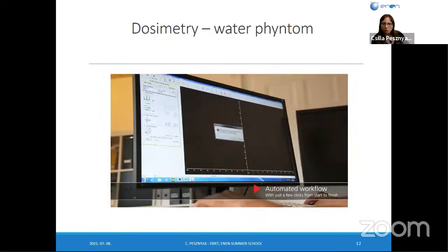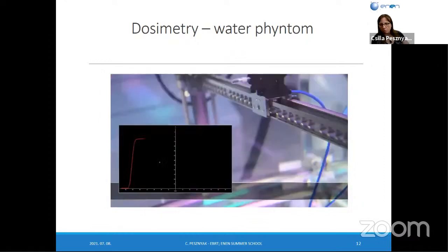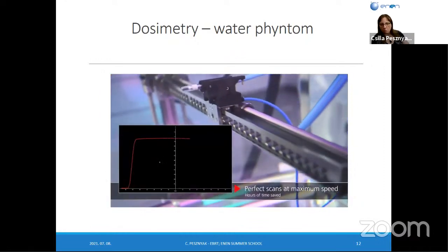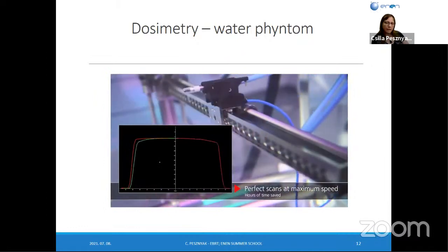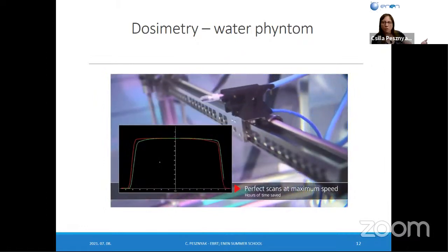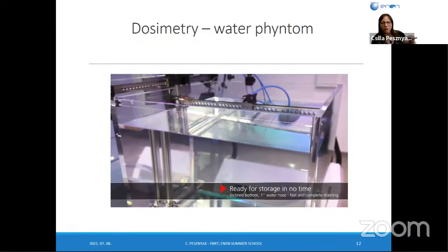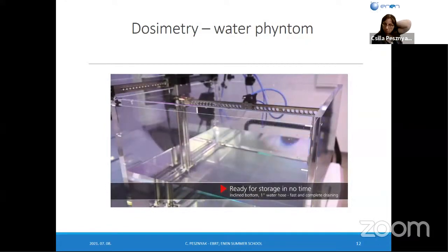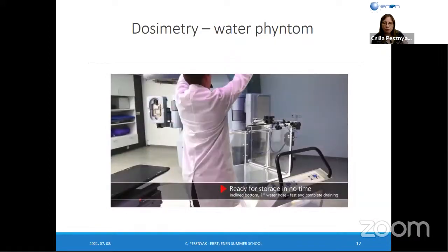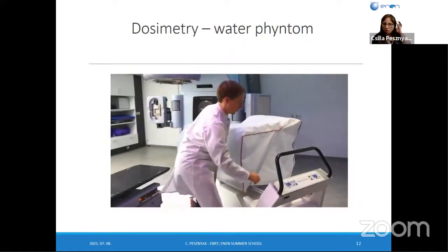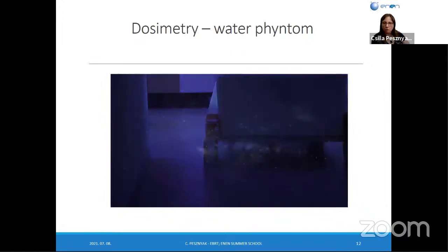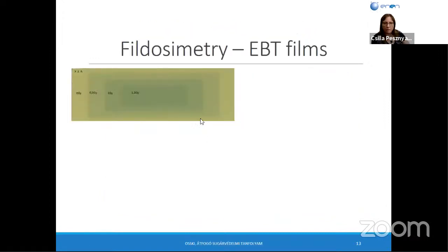It is a reference chamber, and you can see here in the software how the profiles are measured in one direction. We always need to measure in the other direction as well, and after that we can set up in the center line position. When you have finished your work, it is very easy to remove the phantom.